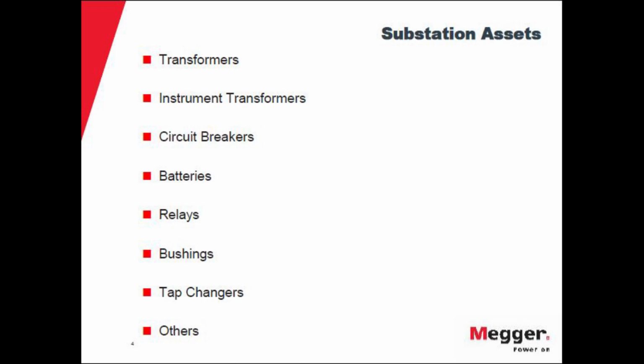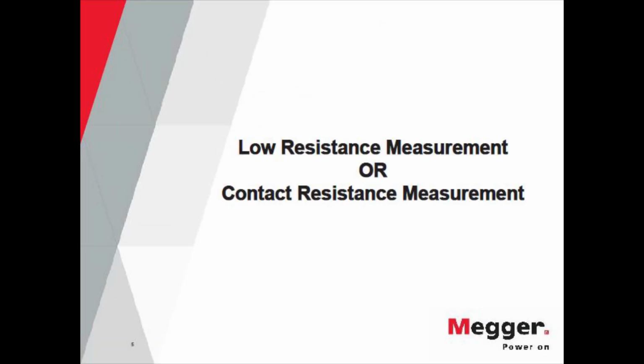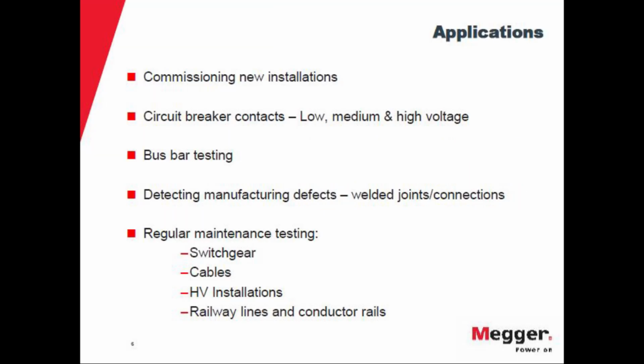The very first one that I want to present is a very basic test, but very helpful and very common in the substation world: the low resistance measurement, or contact resistance measurement. You use this when you're commissioning new installations. You want to use it for circuit breaker testing, doesn't matter what type of breaker, low, medium, or high voltage. You also use it to check bus bar connections, that everything is well connected. You can also use it to detect manufacturing defects in welded joints and connections, to determine if they're well done or not.